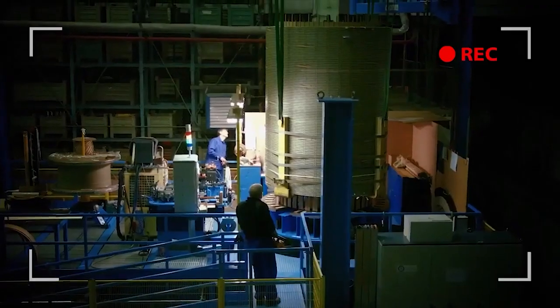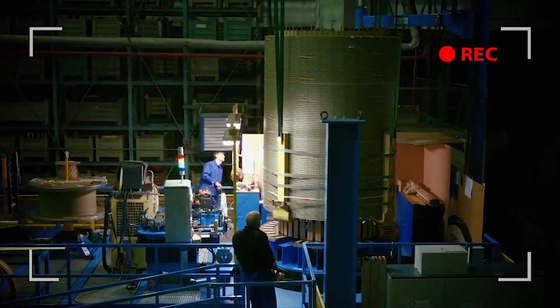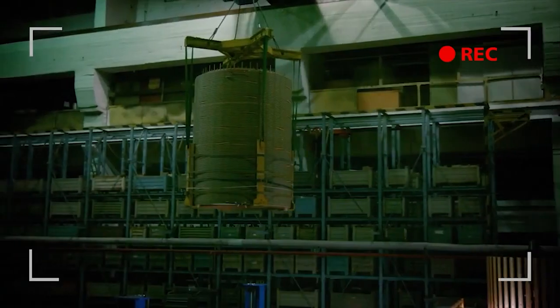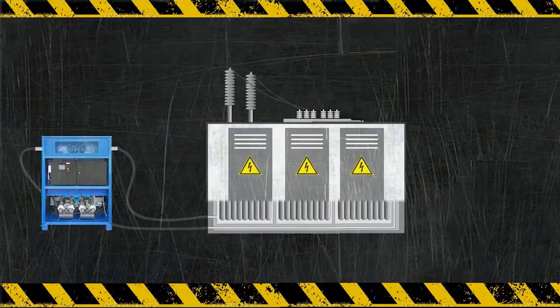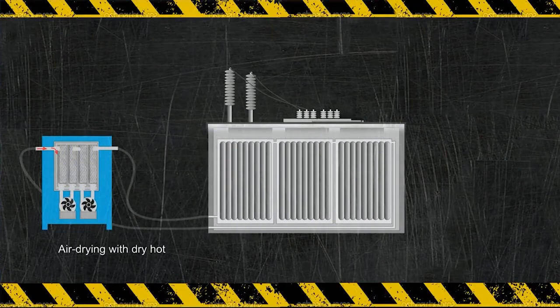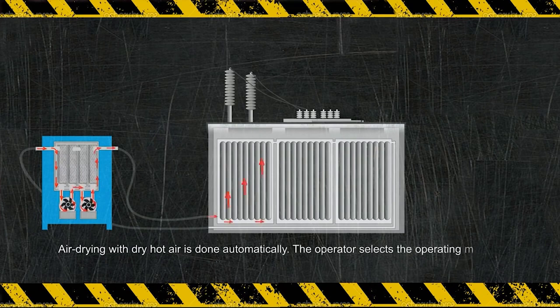During repairs, a transformer must be de-energized and its oil must be drained. Transformer windings may accumulate moisture due to their hygroscopic properties. Dry compressed air is necessary to prevent moisture from entering the transformer.